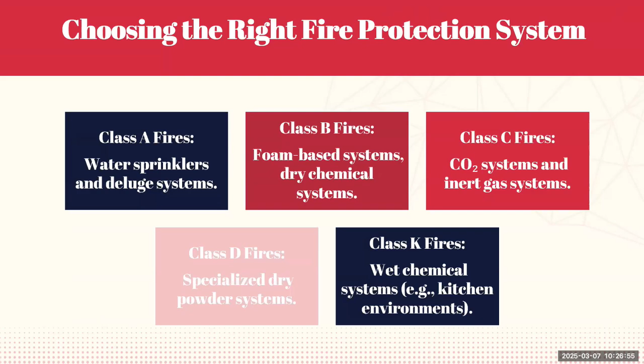Okay, so what are some practical considerations for our system selection? Well, as I said, a very important thing, especially if you have a water-based system, is the fire water availability. You need to ensure that you have adequate supply for water-based systems, so the rings, the sprinklers, and the hydrants. Then also the environmental impact. We need to choose eco-friendly options, for example halon alternatives and inert gases. We also need to consider the plant layout, because some systems might not be adequate to fit in a small area.